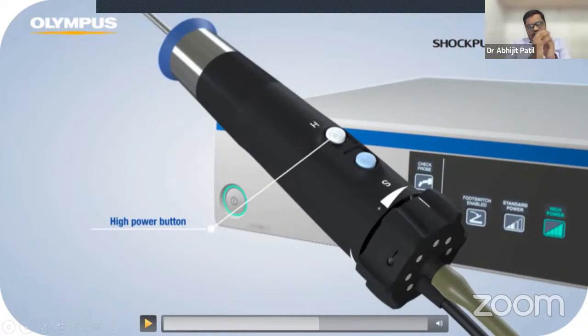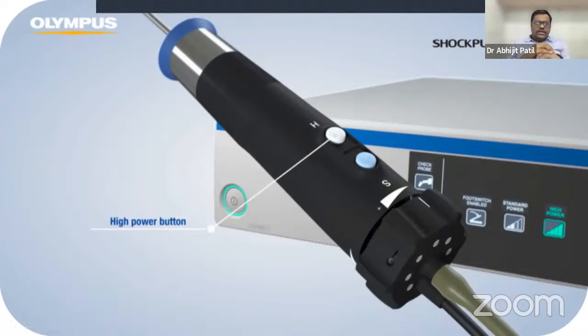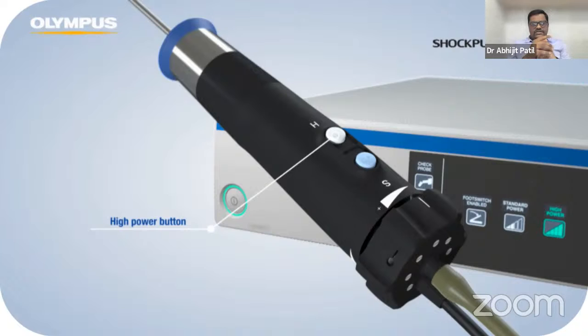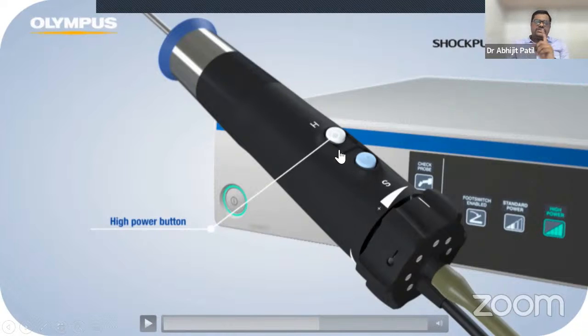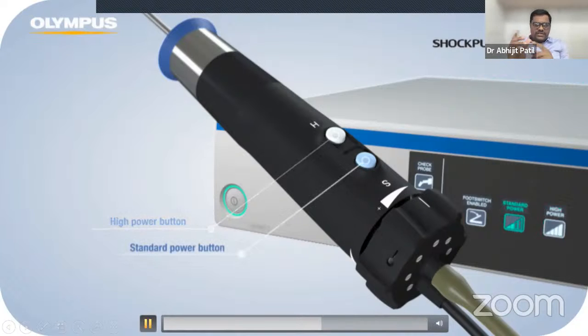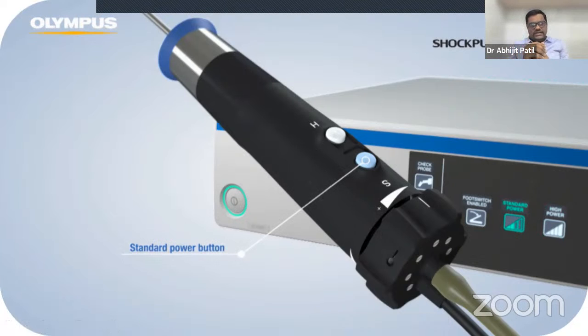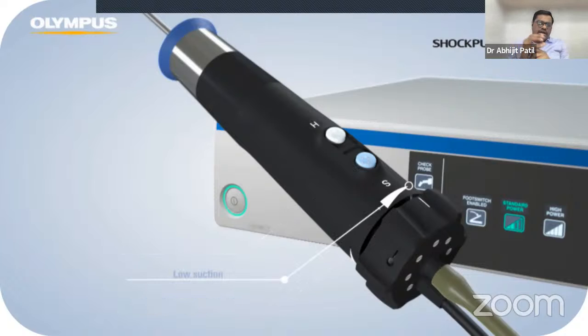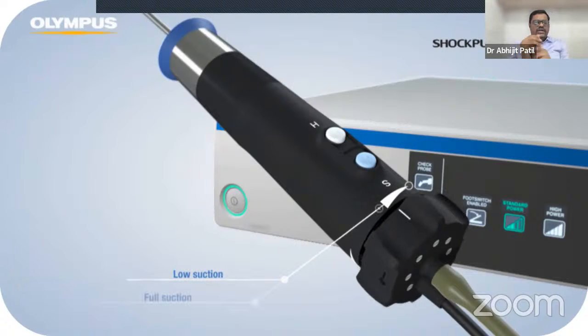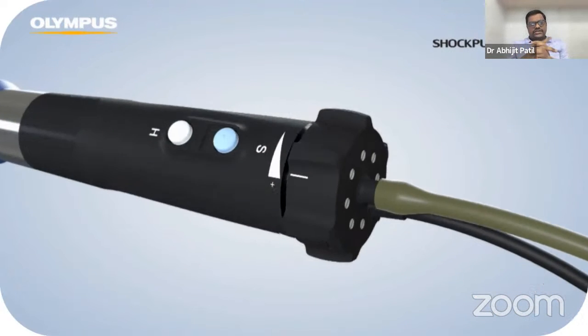Again, a difference between Shock Pulse and Trilogy is that in Trilogy you could control all the components in the generator itself, so somebody else has to do it. In Olympus Shock Pulse, the benefit is that the surgeon has complete control, as there are two buttons on the handpiece which the surgeon can use to decide between a high power button or a standard power button. This is the amount of suction: this is a small suction, this is a high suction. So the surgeon himself can decide, based on the stone density or hardness, whether he wants high or low power, and he can monitor the suction, normal suction versus full suction.